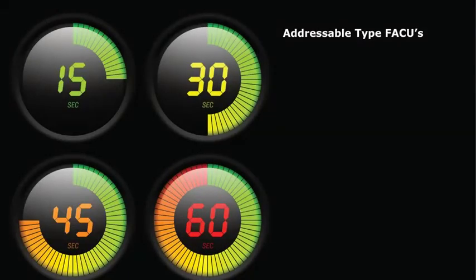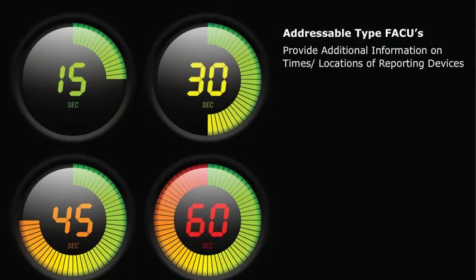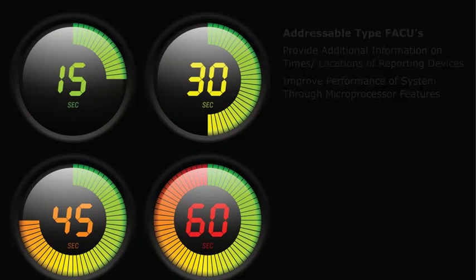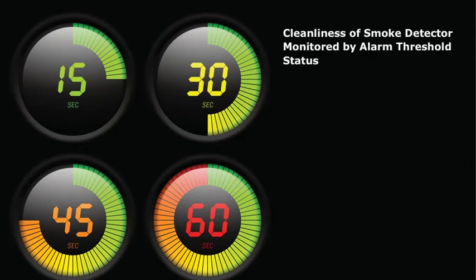Addressable type FACUs provide additional information to the building owner, such as the times and locations of reporting devices. Addressable or analog FACUs improve the performance of the system through microprocessor features that will report exact locations of devices that are reporting, as well as alarm threshold status. Alarm threshold status will monitor the cleanliness of a smoke detector to determine maintenance status and attempt to avoid unnecessary alarms.